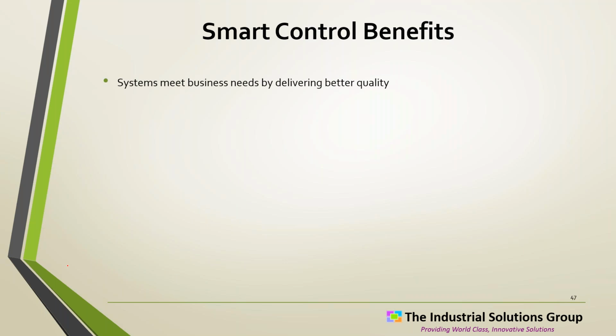And what are the benefits? Well, the reason we put systems in the first place is we've got to meet some core business need. We got to make a product, a certain quantity of product, a certain quality of product. And if we've got a combination of equipment and systems that aren't doing a good job of that, then why even spend the money on it? That usually comes down to, are we getting the right flows, temperatures, pressures, heat transfers out of the equipment? A lot of commissioning was done when these systems were put in new. Are they continuing to run that way day in and day out?